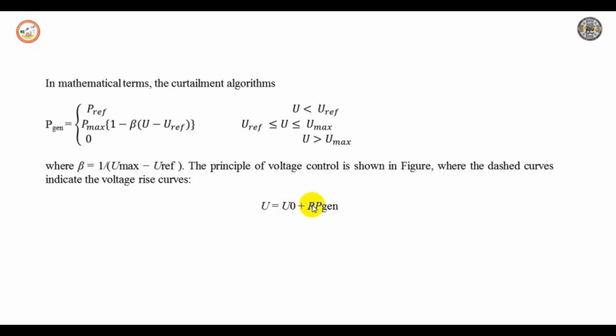So where you can see that for maximum production, it is again assumed that there is no exchange of reactive power between generator and grid. The level of consumption is represented by U naught for a situation without generation. In the previous figure, U naught is the point of intersection with the horizontal axis. At the intersection with the horizontal line, P gen is equal to P max. This is the voltage for maximum production, that is U is equal to U naught plus R P max.